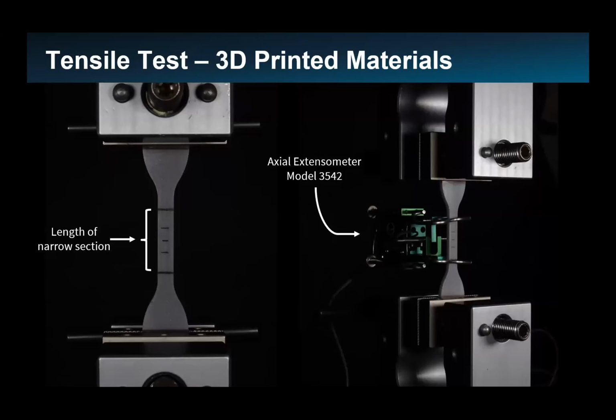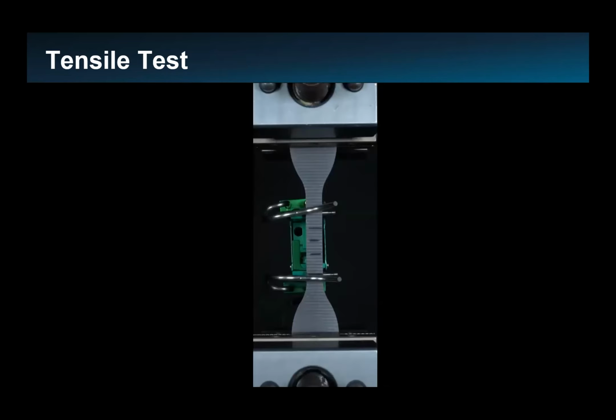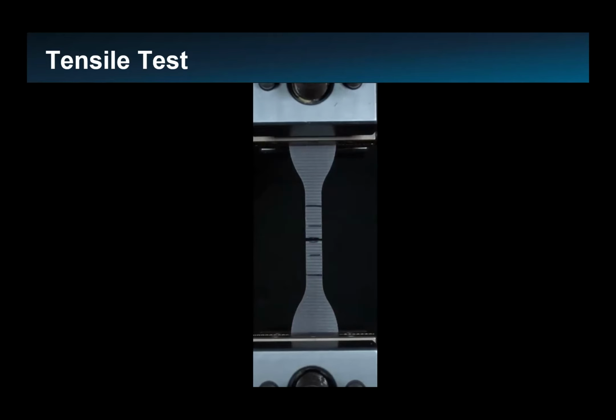And once we have the specimens, what we need to do was to perform several tensile tests, as you can see in the figures. So in the figure on the left, you can see some marks that are called the length of narrow section, where the specimen is allowed to fail. And in the figure on the right, you can see the setup of the specimen and the appropriate extensometer for this type of material. As I mentioned, this is a rigid plastic, so we need to use this specific type of extensometer. This is a short video where you can see how this rigid plastic failed. And as you see, the failure is exactly at the middle for this type of orientation.